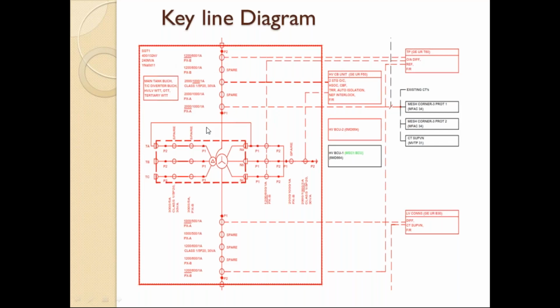These are the ratings for each CT. For example, for a 400 kV substation, in the UK we normally deal with 3 types of substation: 400 kV, 275 kV, and 110 kV or 132 kV. For the 400 kV CT rating, there is a catalog based on NGTS standards, and you can pick the CT from it. If it is a new transformer, there is no need to worry about the ratios; we can go for 1200 per 1 amp.